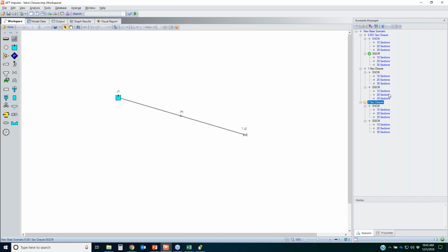That's the key thing here, not just how do you understand cavitation. The whole idea is how do you eliminate cavitation, or how do you reduce the level of cavitation? Well, if I take a little bit longer to close the valve, that will potentially help dampen out the pressure spikes that you might see. So that's where I had my other scenarios.